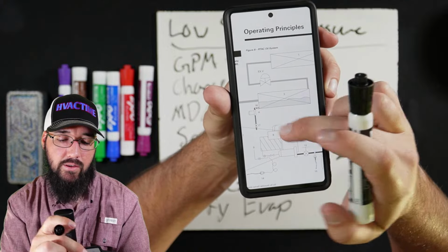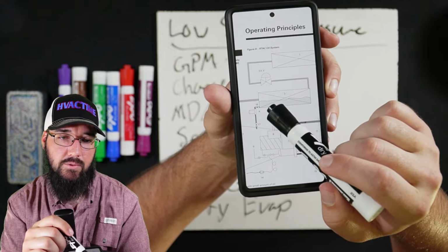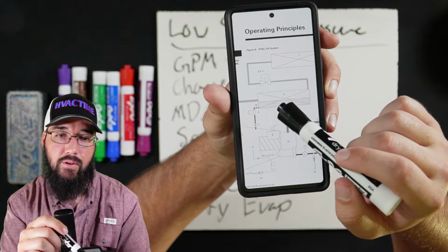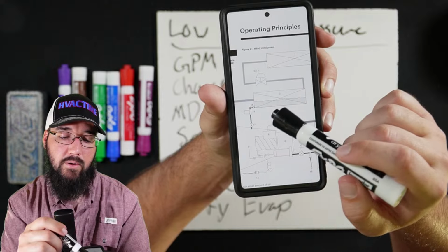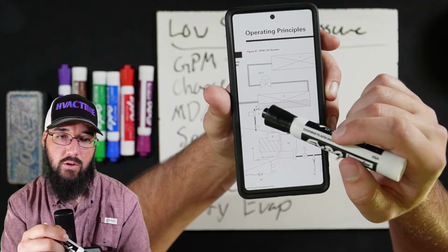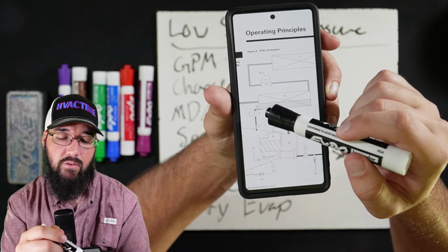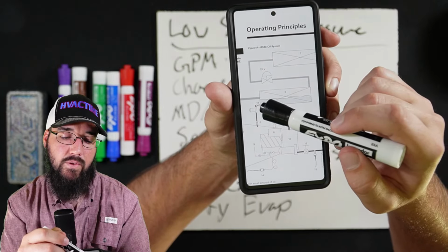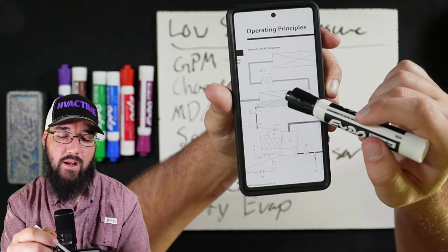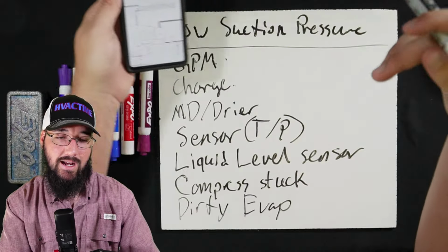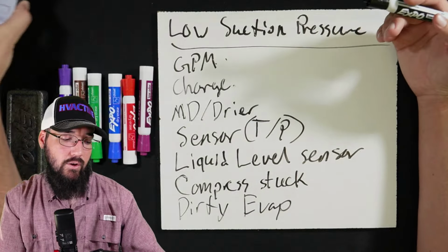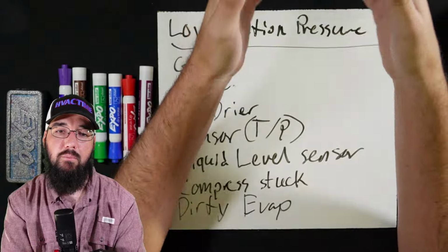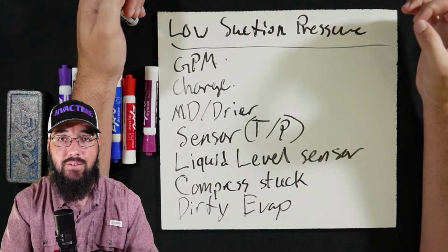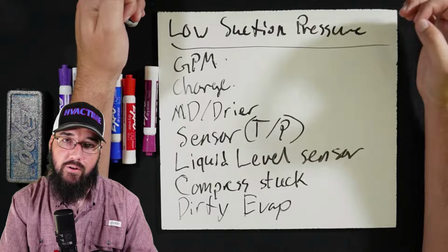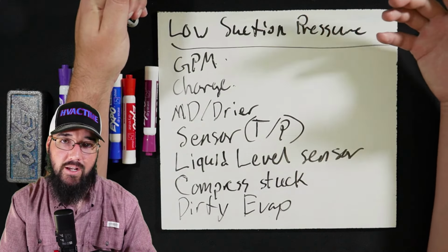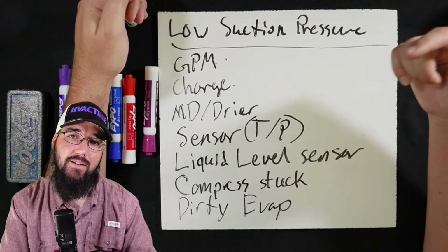That being said, you'll see that it is very specific that the oil return line comes off the bottom of the evaporator down here, and I do think that is correct. There is a line that comes right off the bottom, because we have such a low liquid level in here. The very bottom of this evaporator is where that oil is going to stack. If this oil got in here too concentrated, if you had a really high oil charge, that could make it so the refrigerant is getting past the separator at a higher rate.